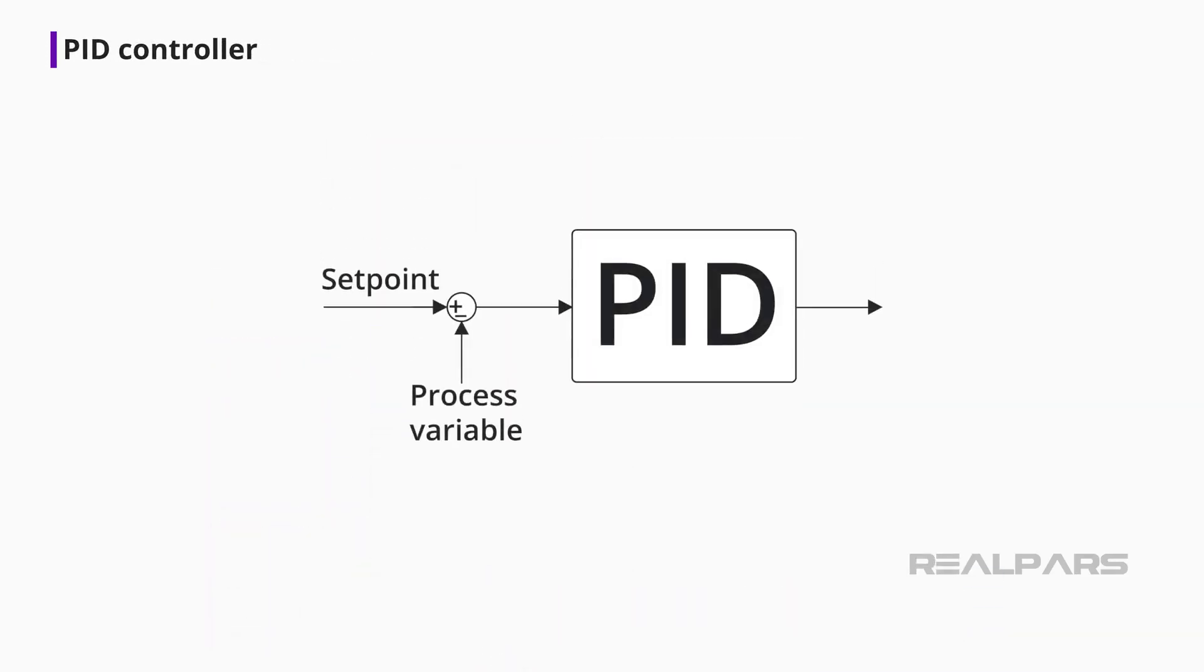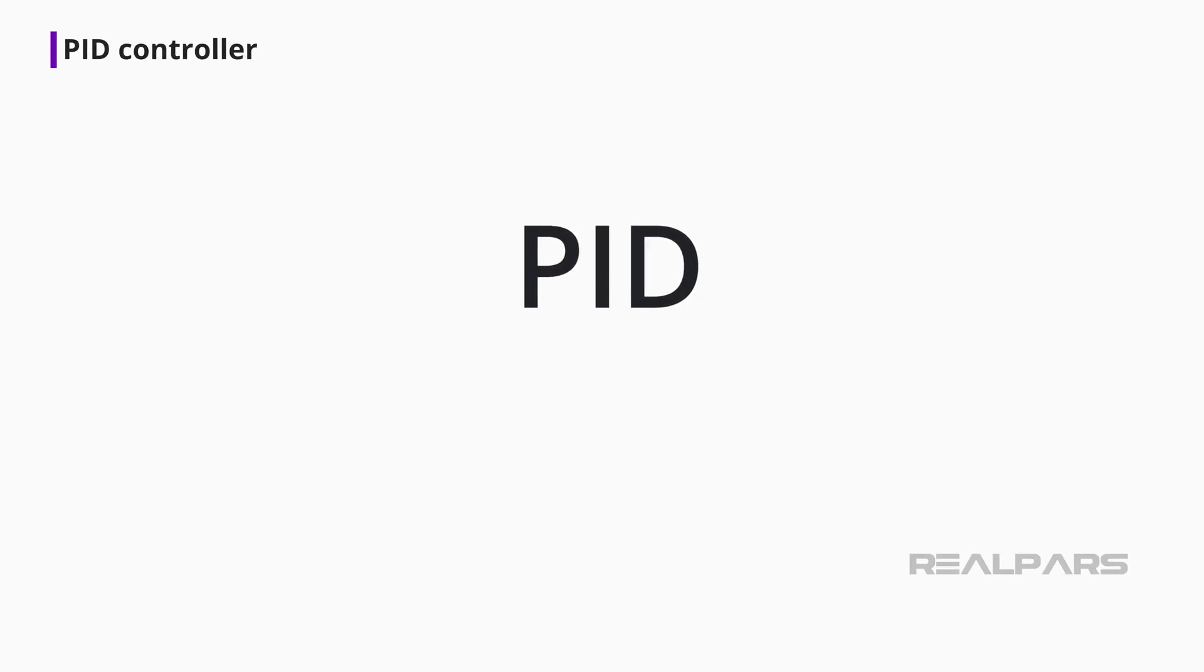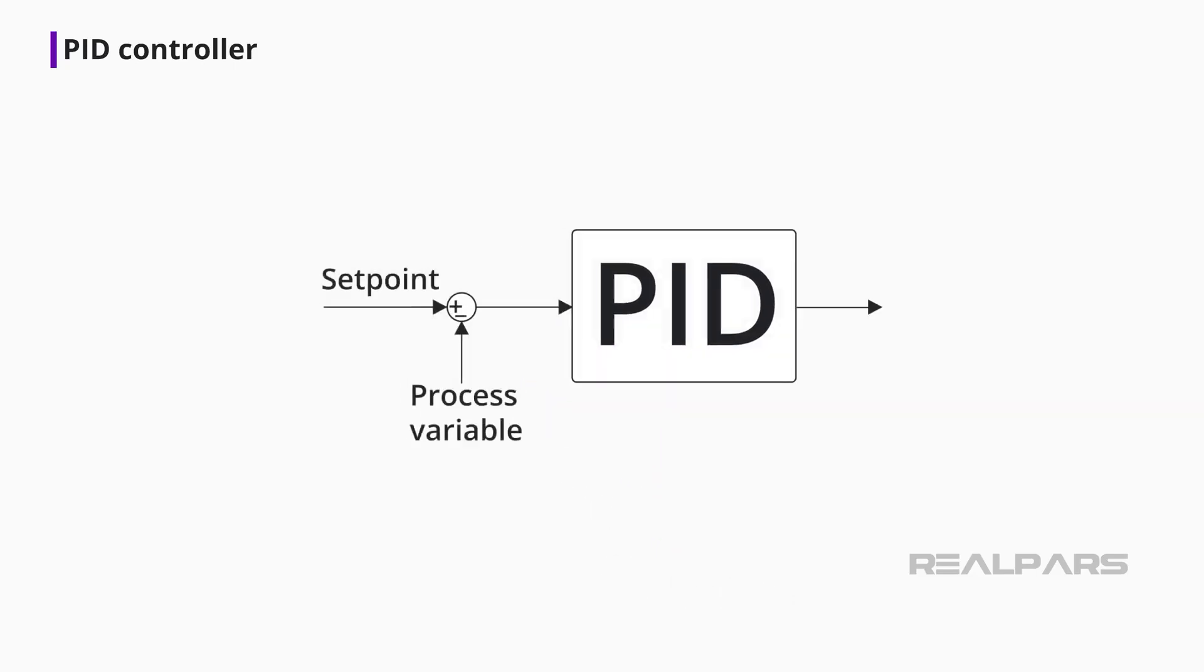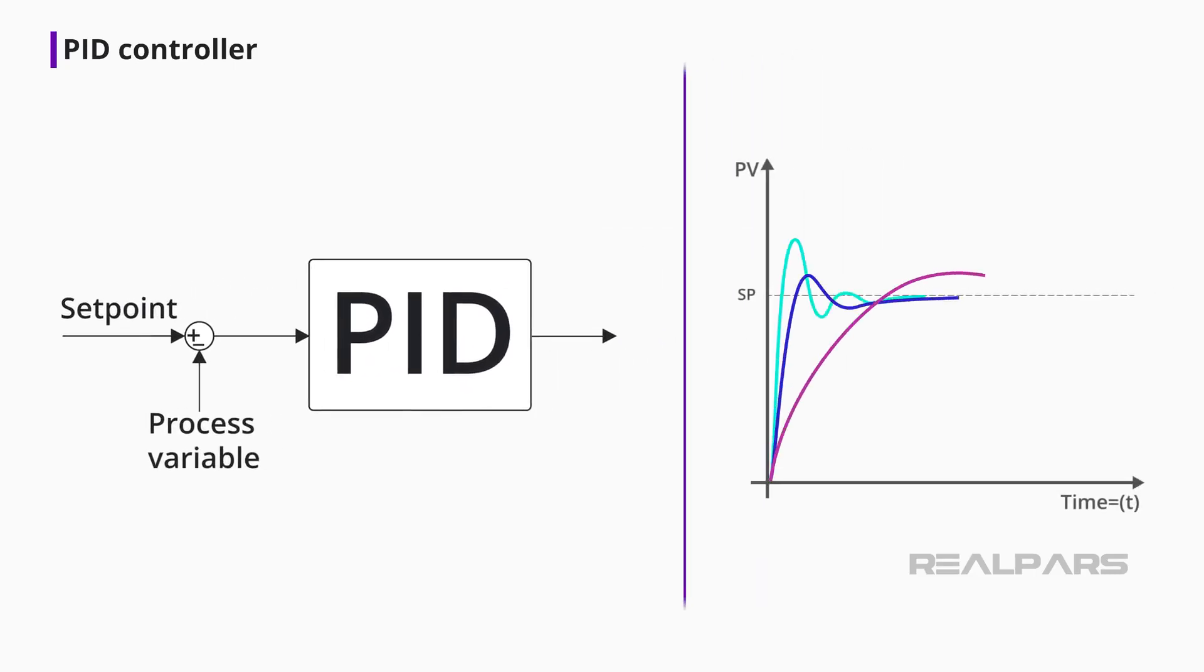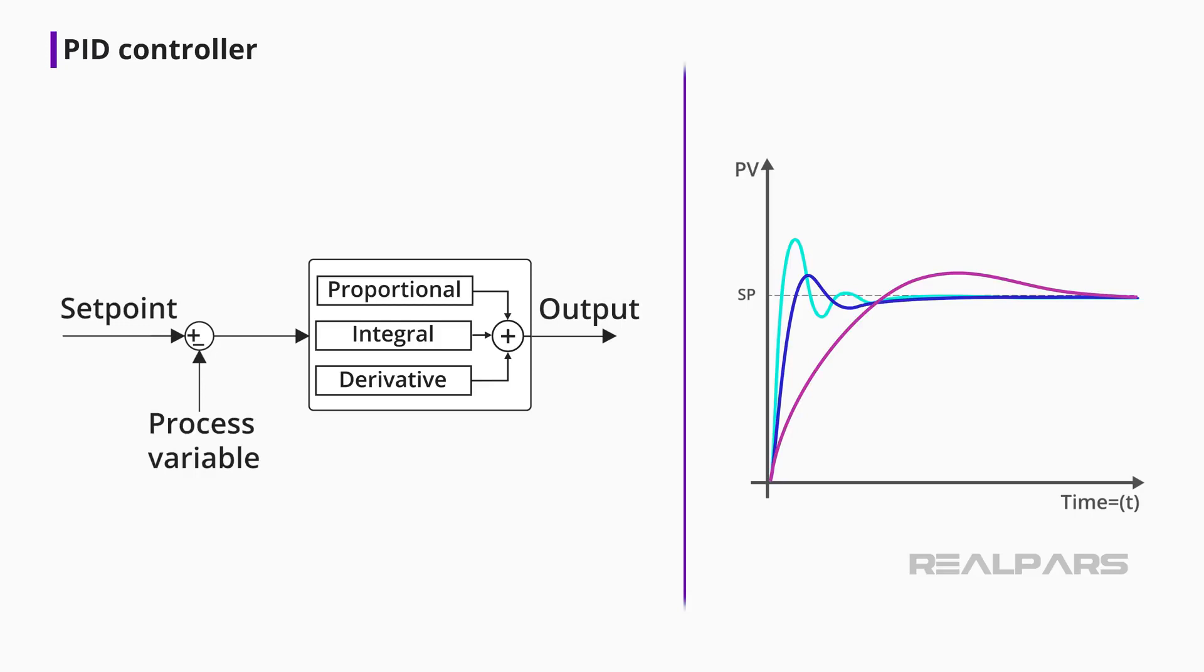Now we can move on to talking about a PID controller. P stands for proportional, I stands for integral, and D stands for derivative. Because every process responds differently, the PID controller determines how much and how quickly correction is applied by using varying amounts of proportional, integral, and derivative action. Each block contributes a unique signal that is added together to create the controller output signal.